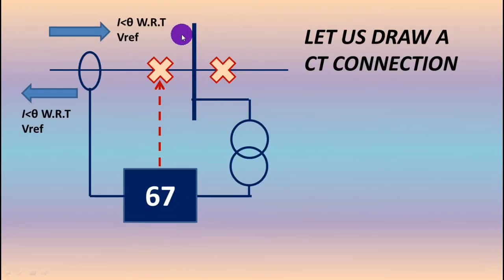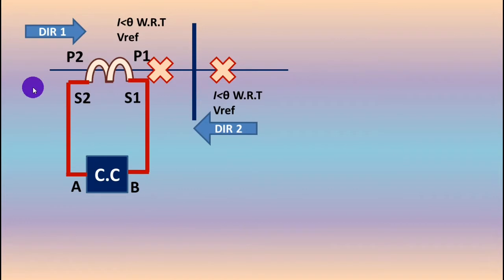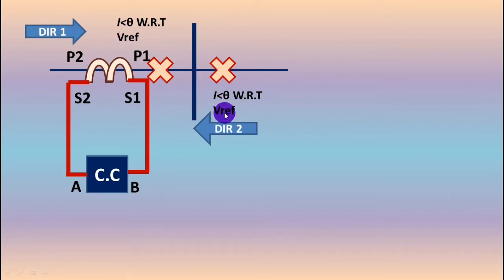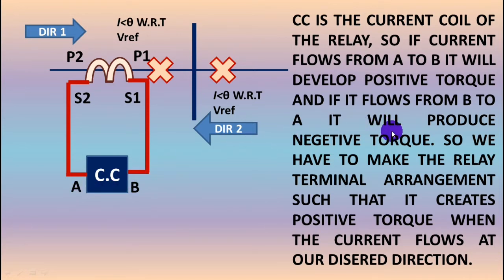The CT sees the same fault current having the same phase relationship with the reference voltage — once for current travelling from left to right and once for current travelling from right to left. So these are the two conditions: I at angle theta, I leading theta with respect to V reference — once flowing from left to right (direction 1) and once from right to left (direction 2). Both have the same I with respect to V reference; the phase angle relationship with reference voltage is the same for both cases.